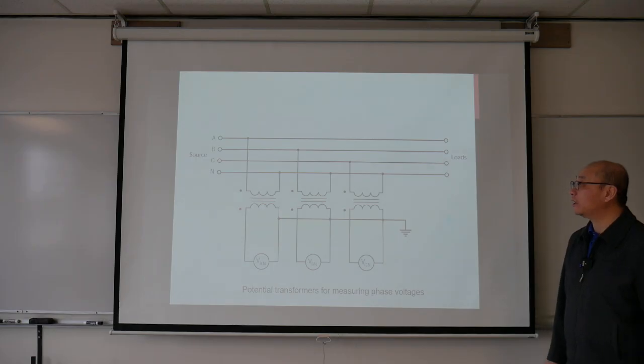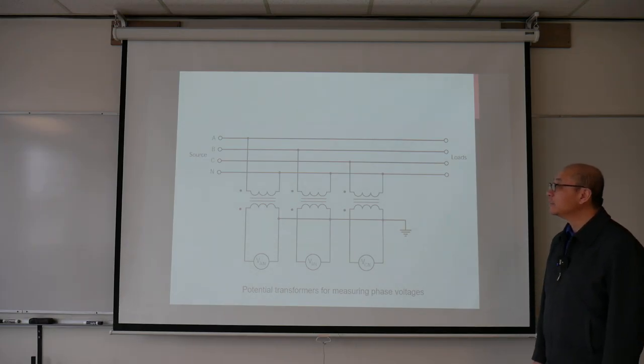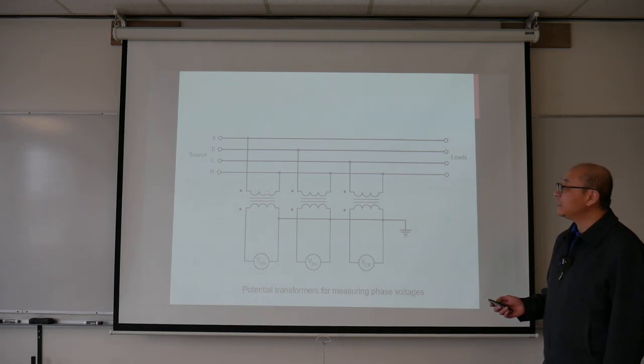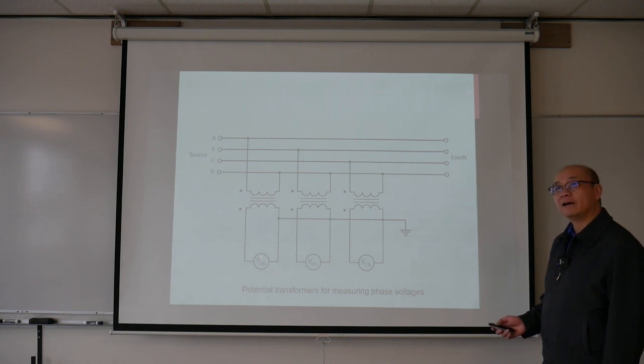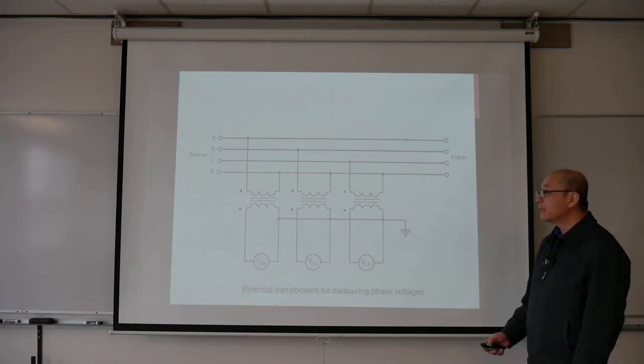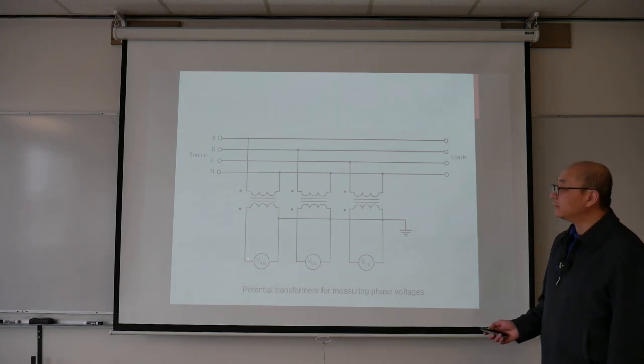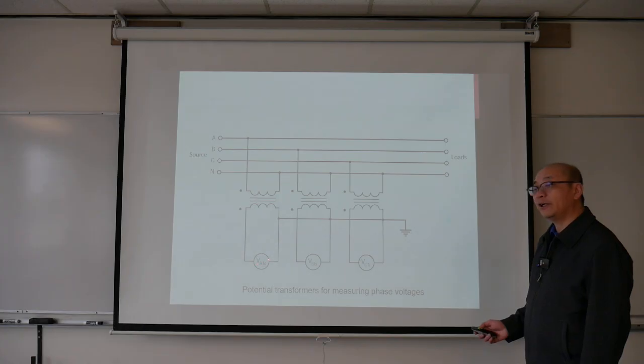Here's a picture showing three potential transformers trying to measure the phase voltage in this three-phase circuit. The primary side of each potential transformer is connected between one of the lines and the neutral, so it's measuring the phase voltage. On the secondary side, we use a step-down potential transformer to indicate the phase voltage. Normally, for a standard potential transformer, the secondary output is usually 120 volts.